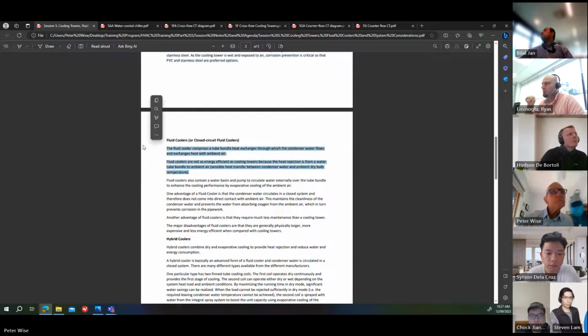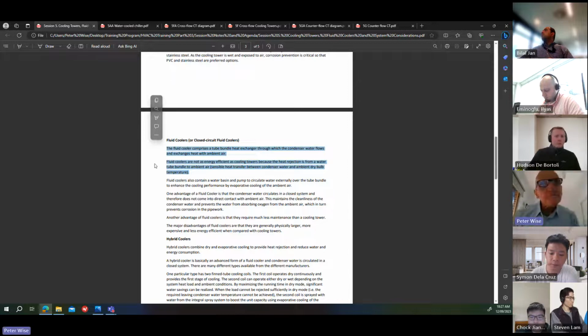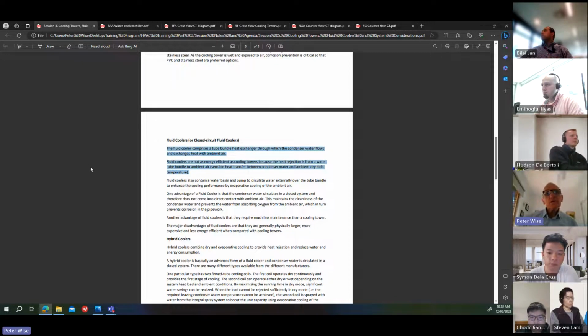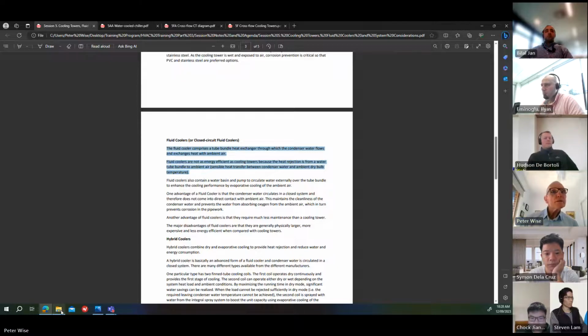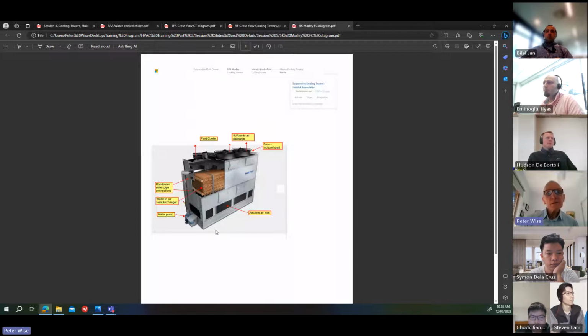Okay, fluid coolers. Fluid coolers comprise a tube bundle heat exchanger through which the condenser water flows and exchanges heat with ambient air. I'll just show you a diagram of a fluid cooler. So in this case, it looks a bit like a counterflow cooling tower. It's a very similar principle, but air comes in the bottom through these openings and then passes up through a tube bundle. So you don't have a fill as such. It's actually a tube bundle heat exchanger. So condenser water flows through the tubes and the air passes over the tubes and then discharges out the top. So that's a dry cooling process. There's no direct contact between the water and the air.